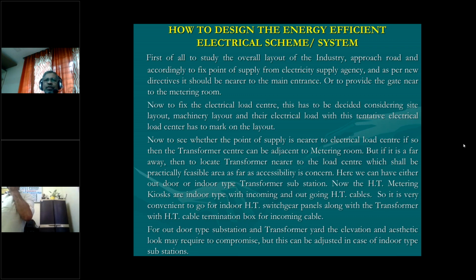For an outdoor type substation and transformer yard, the elevation and aesthetics may require a compromise, but this can be adjusted in the case of an indoor substation. Now, I would like to focus on the outdoor one: you have seen the switchyard, a huge switchyard, say 6 meters by 20 meters or 12 meters by 30 meters, something like that. You have seen it in many industries.